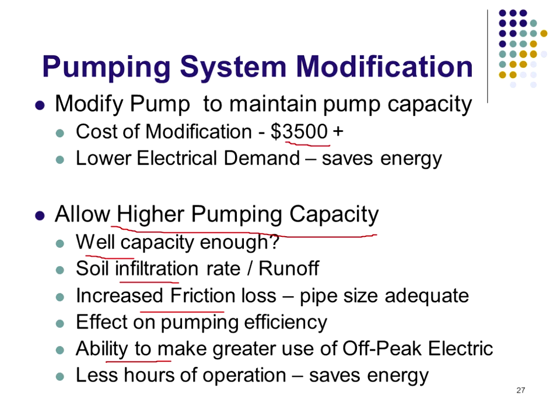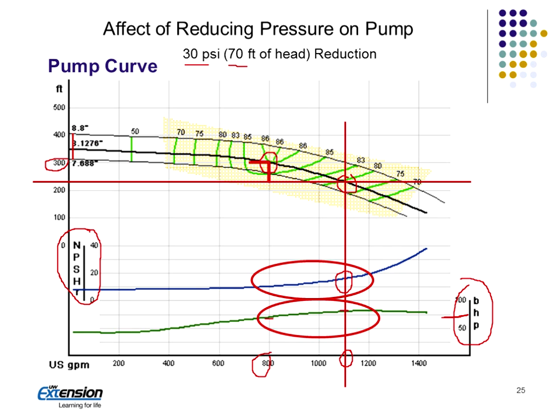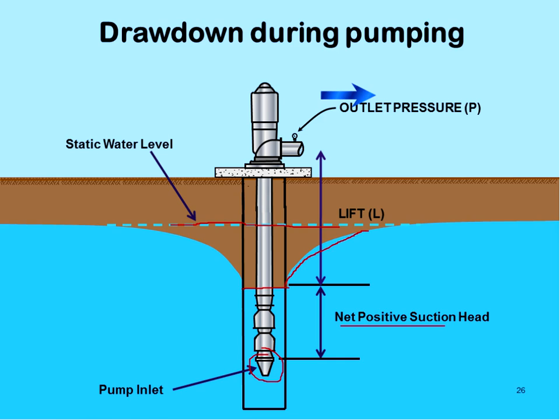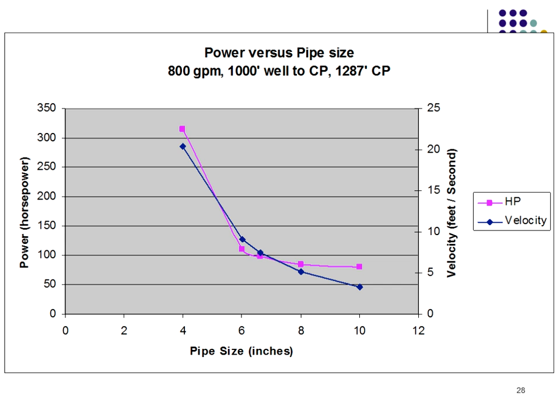If we can pump more water, it does allow us a greater possibility to use off-peak electric, which can be an advantage because it reduces the number of hours of operation. So let's back up to this graph for a minute. These green lines, this is efficiency. Every pump's going to be a little different. You can see this one, we're kind of at the sweet point here. It's about 86% efficiency. By moving this down, we drop to 80%, which is still excellent as far as pumping capacity. Anything above 75% is considered good. But that's another thing we need to look at when we change that pumping rate, because it can affect the efficiency as well.